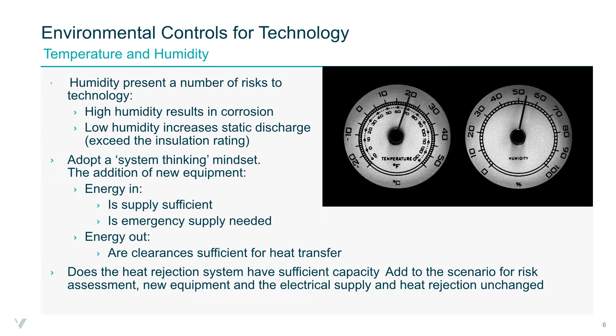So what I would suggest is, even at a very high level, if you're a stakeholder in system replacement, adopt that system thinking mindset. So we've got energy in. Is the supply sufficient? These are some very basic questions, I guess, that can be considered. Is the device currently covered by an emergency supply, an uninterruptible power supply? Is it one of the circuits on the emergency generator? And when we're talking about energy out, are the clearances sufficient for heat transfer? Does the heat rejection system have sufficient capacity?